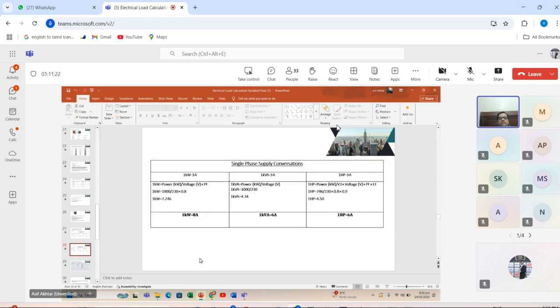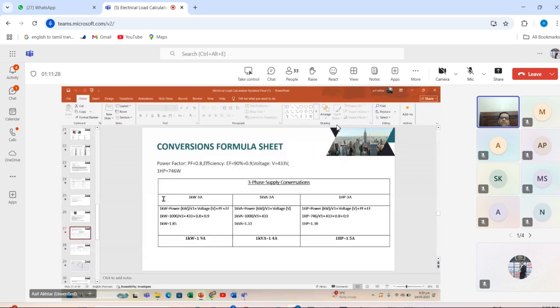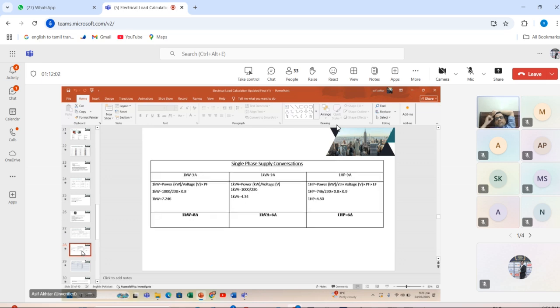I am talking about the conversion formula for three-phase supply. If you do this calculation, you will get the figure: 1 kilowatt is 1.9 ampere, 1 kVA is 1.4 ampere. This is the formula I am using: 1 kVA is power divided by root 3 multiplied by voltage, multiplied by cos theta. You will use the power factor in this formula, and the rating is 0.85. If you use all these calculations, you will get 1.44 ampere. And this is the single-phase conversion. We use the power equals VI formula.